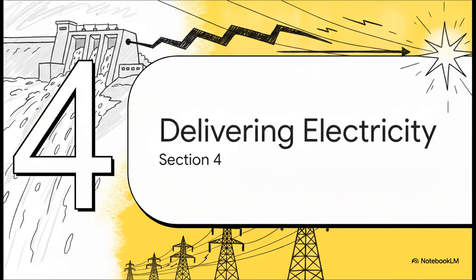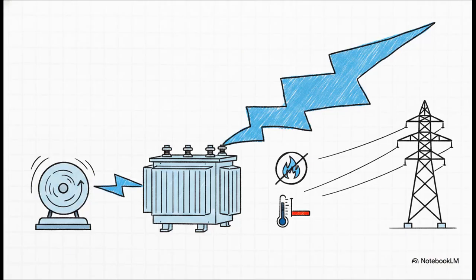Section 4, delivering electricity to consumers. While the water itself is returning to nature, its extracted energy is embarking on a completely different, high-speed journey out to the power grid. Before that power can travel miles and miles across the country, it hits the step-up transformer. To make this journey economically and efficiently, the transformer massively boosts the generator's voltage. For instance, it might step it up from 11 kilovolts all the way to 132 kilovolts, or even 22 to 400 kilovolts. Now, why do we do this?